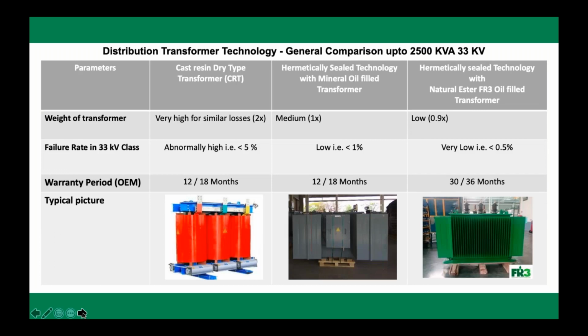Typical pictures I brought for everybody's comfort. So just don't try to find out which make the transformer is, but that's how it looks. The FR3 fluid people are giving, I have nothing to do with that, but a lot of OEMs give more and more guarantee and warranty on that. Nowadays 3 years has become typically a standard practice. Whereas for dry type or mineral oil, people still restrict to 1 year, because even OEMs are afraid of having limitations on dry type transformer failure.